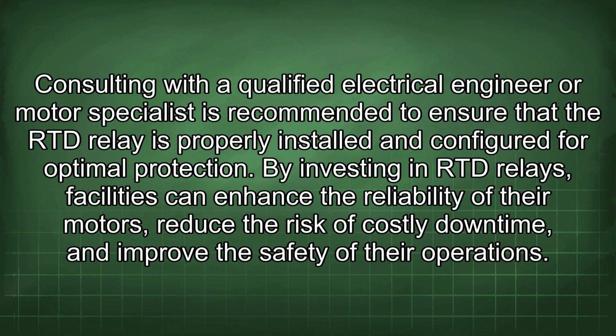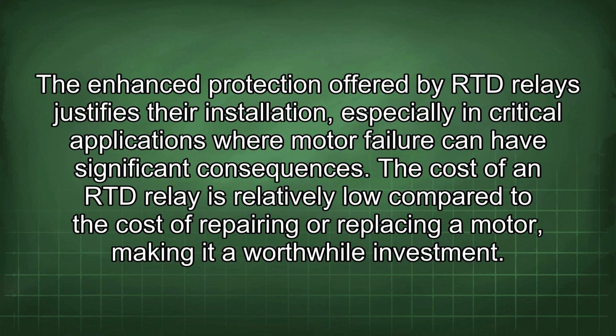By investing in RTD relays, facilities can enhance the reliability of their motors, reduce the risk of costly downtime, and improve the safety of their operations. The enhanced protection offered by RTD relays justifies their installation, especially in critical applications where motor failure can have significant consequences. The cost of an RTD relay is relatively low compared to the cost of repairing or replacing a motor, making it a worthwhile investment.